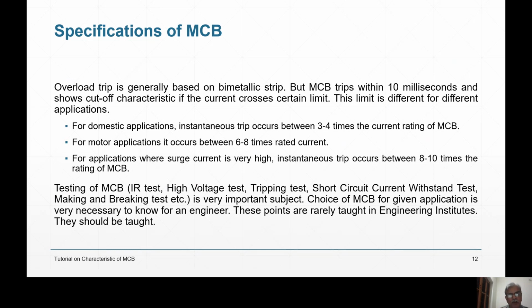where 6 times the rated current is the starting current, and it is going to pass for 7 seconds, the MCB should not trip instantaneously before 6 to 8 times the rated current. Its duty is different. Its requirement is different. Its type is different. Therefore, MCB types B, C, and D. B is for domestic applications, C is for motor application, D is for applications where you have devices which take a very high surge current, some 8 or 10 times. So these things are there.